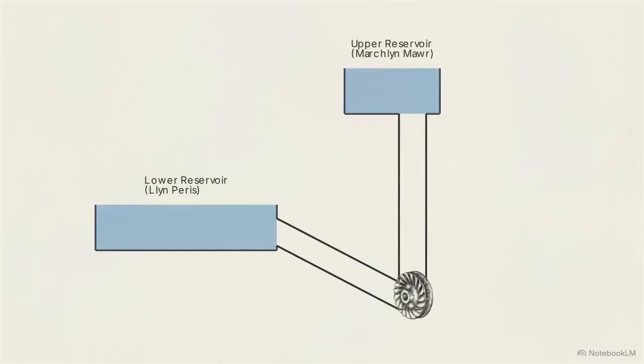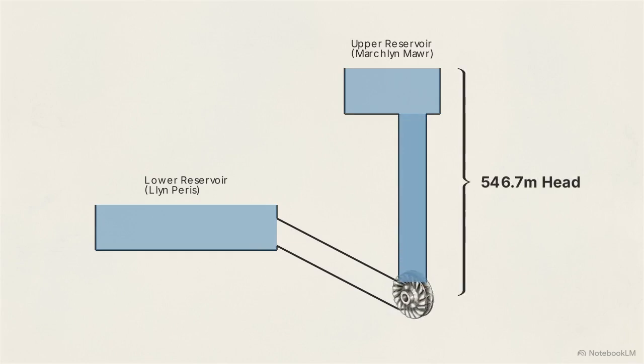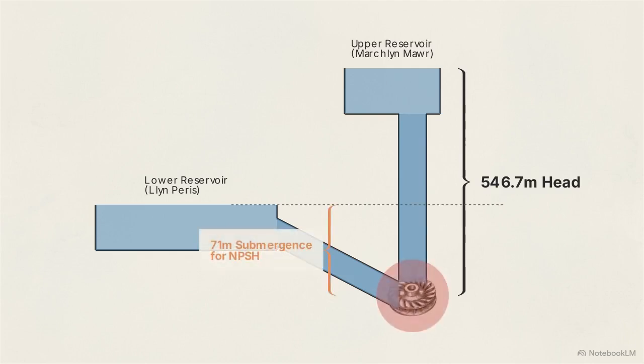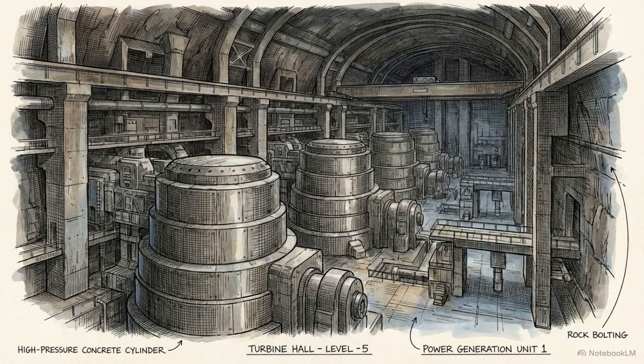This cross-section illustrates the primary energy transfer. Water from the upper reservoir drops 546.7 meters down a vertical shaft, striking the Francis turbine runner with extreme hydraulic force. To prevent the resulting pressure fluctuations from causing destructive cavitation on the metal blades, civil engineers positioned the turbine floor exactly 71 meters below the surface level of the lower reservoir. This guarantees the necessary net positive suction head. Managing this highly pressurized hydraulic impact without destroying the cavern's machinery is the strict physical requirement for generating massive electrical output.